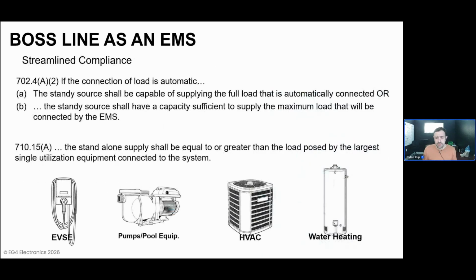Now, that energy management system capability not only increases performance, but like I said previously, streamlines compliance. So there are a couple of key code sections that an energy management system will enable compliance to significantly easier than the alternate paths that are required. The first essentially states that if the connection to a load is automatic, the standby resource should be adequate to power the entire potential load present by the property or the home being supplied by the power source. What that means is for a home with a 200 amp service, in theory, on paper, the full load of that home that should be able to be deployed is 200 amps. Obviously, that would well oversize the inverter needs for most homes, where we already talked about generally most homes pull at most 40 amps during their peak demand usage.